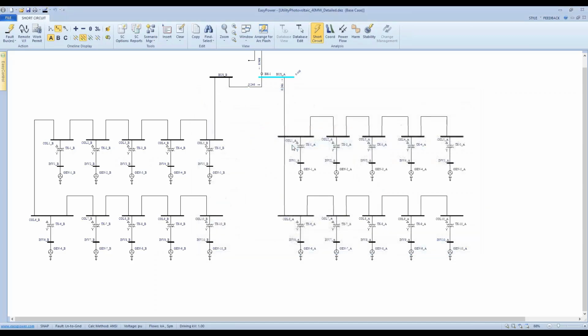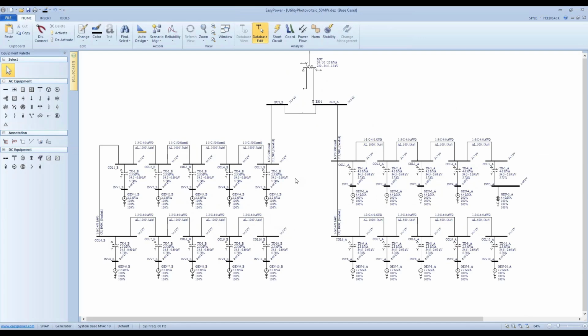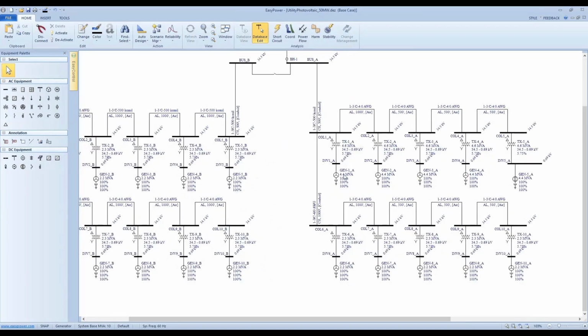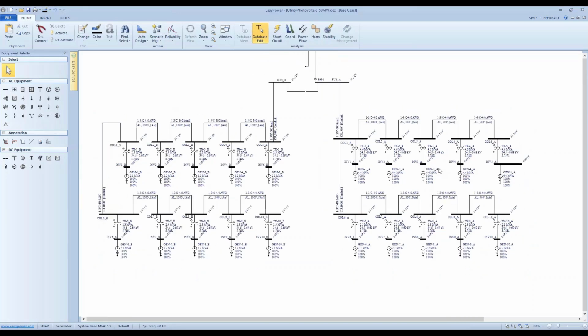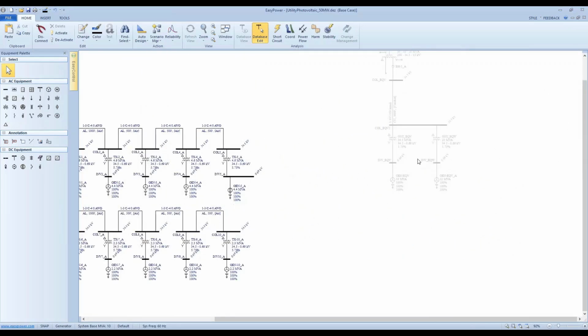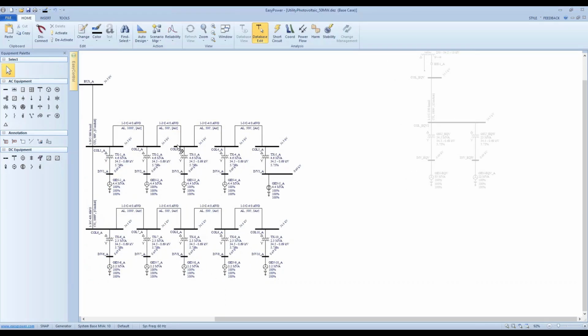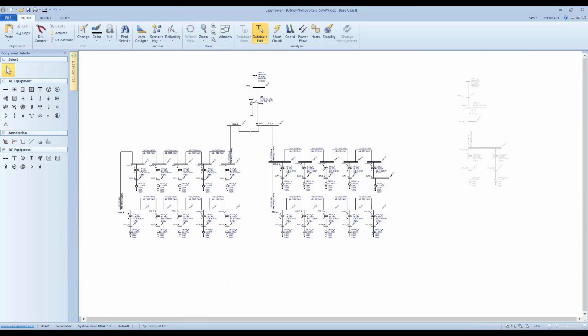I have a 50 megawatt case, which is exactly the same as the 40 megawatt case, the solar design, but I replaced the inverter from 2 megawatt to 4 megawatt on inverter 1 through inverter 5A, right? So I have 2 groups, 2 types of inverter. So what we need to do is to use 2 lumped inverter and pad mount transformer equivalents to represent each type of inverter, and aggregate the total amount of generation from each type together to get your equivalized generator. Make sense? For instance, I have 15 2 megawatt generators. So what I have here should be a 30 megawatt, 33 MVA rated generator, which is a case.